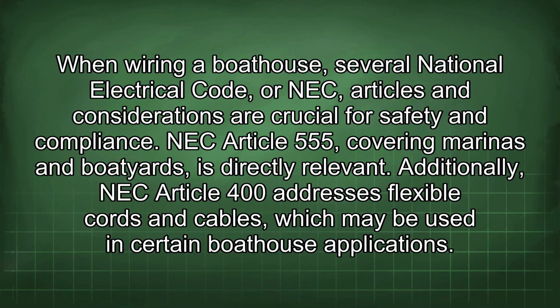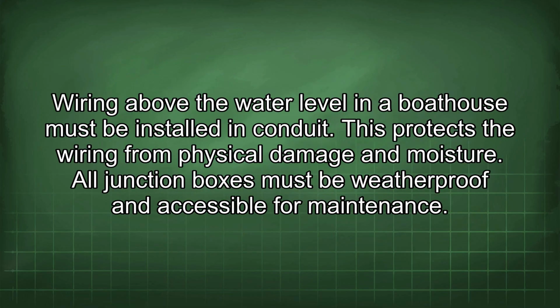When wiring a boathouse, several National Electrical Code or NEC articles and considerations are crucial for safety and compliance. NEC Article 555 covering marinas and boatyards is directly relevant. Additionally, NEC Article 400 addresses flexible cords and cables, which may be used in certain boathouse applications. Wiring above the water level in a boathouse must be installed in conduit.